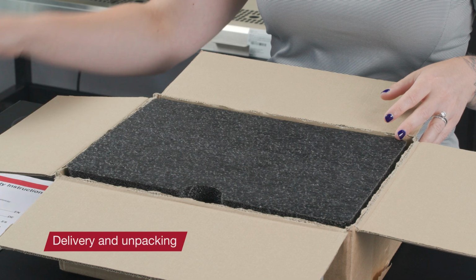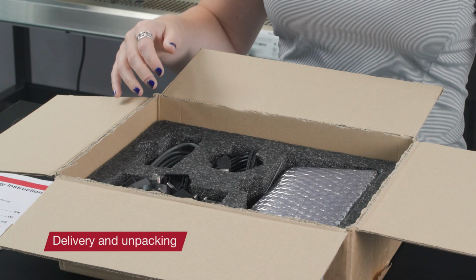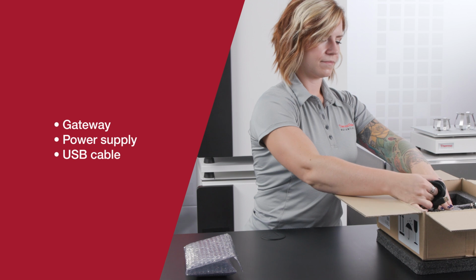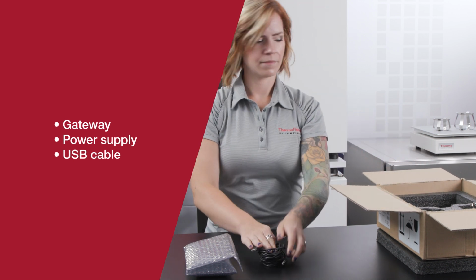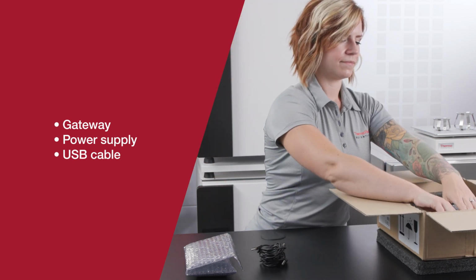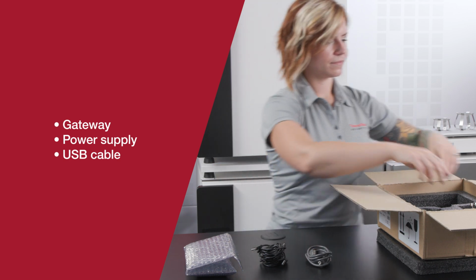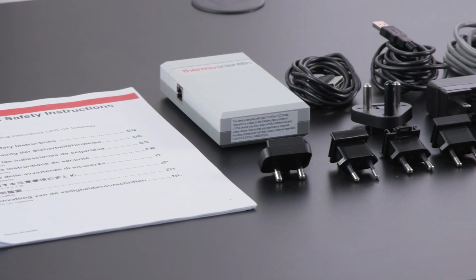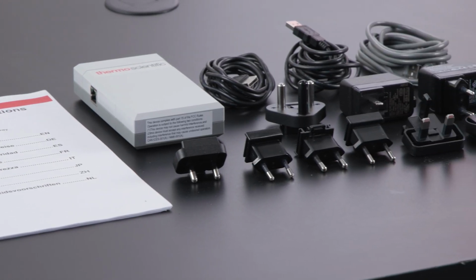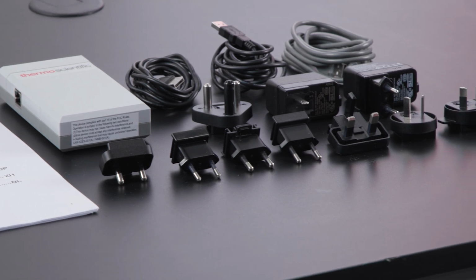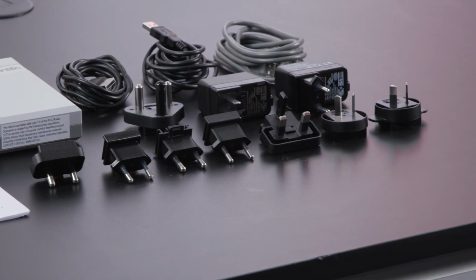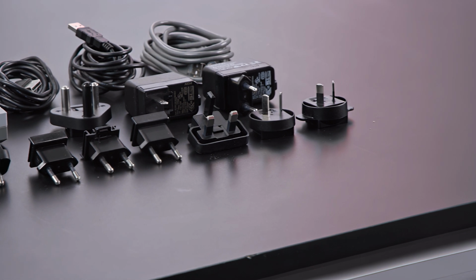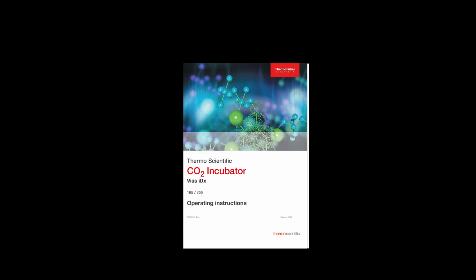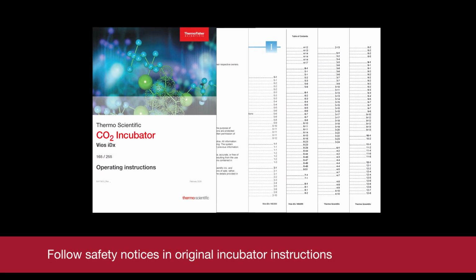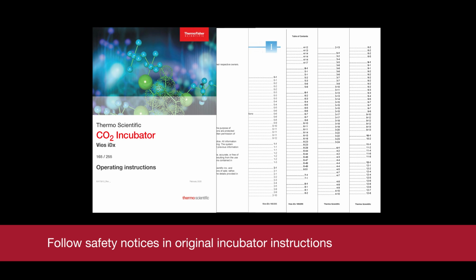When your gateway arrives, check that none of the components are missing. You should receive the OPC UA gateway, a 100 to 240 volt power supply, and a USB-A to USB-B connector cable. Also, make sure all of the components have been delivered and that the packaging, device, and components are undamaged. If anything is missing or damaged, contact customer service immediately. The instructions shared in this video are supplemental to the original operating instructions that come with Vios iDx incubators. They don't replace them.